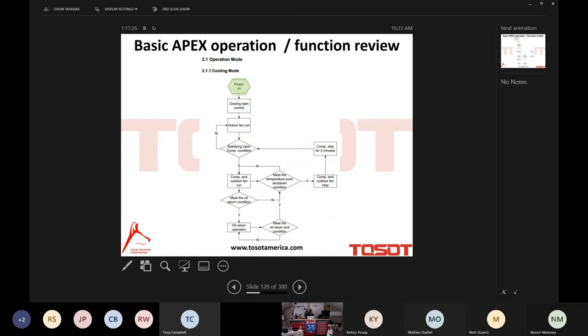But here, we see the system is powered on. We get an active call for cooling. First thing that happens is that the indoor fan begins to run. Then the compressor and the outdoor fan begin to run. Guys, if the system has been running at a low frequency, a low RPM, now you guys know what I'm talking about when I say low frequency, low RPM. If it's been running at a low frequency for a long time, the system is going to enable the oil return control to bring the oil back to the compressor.